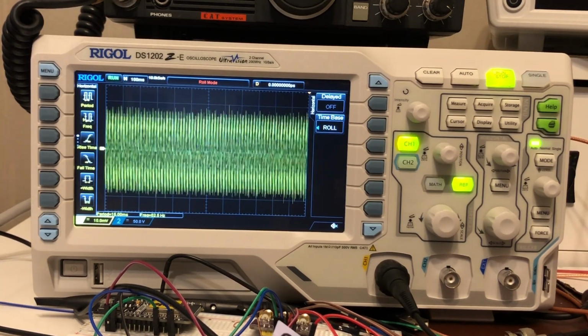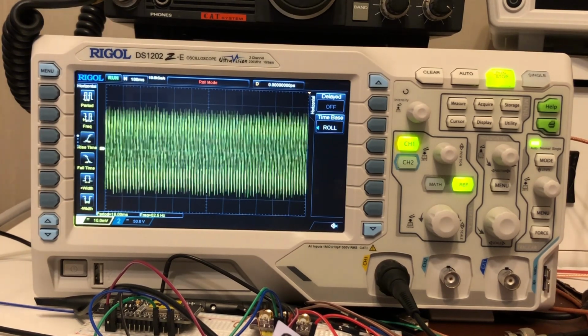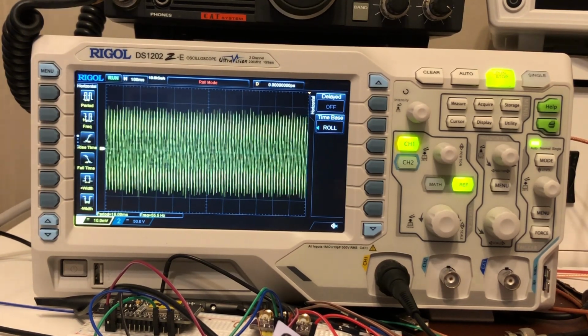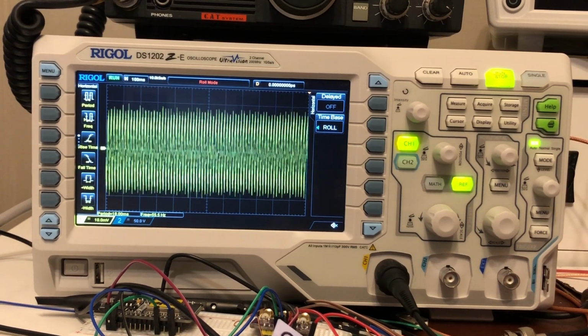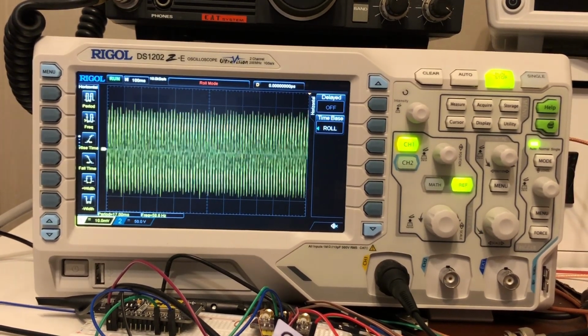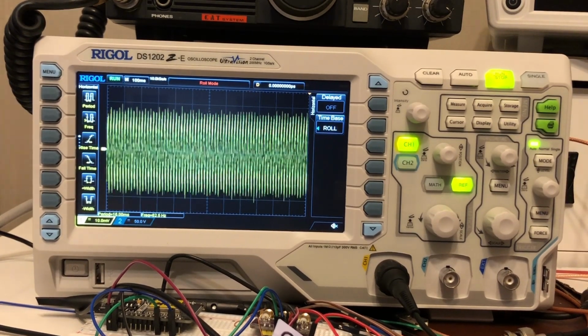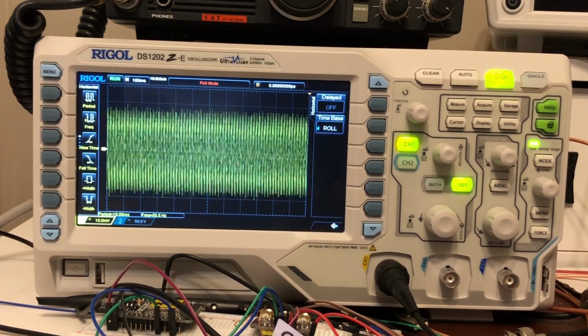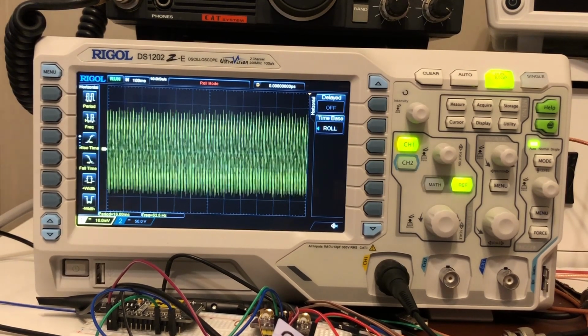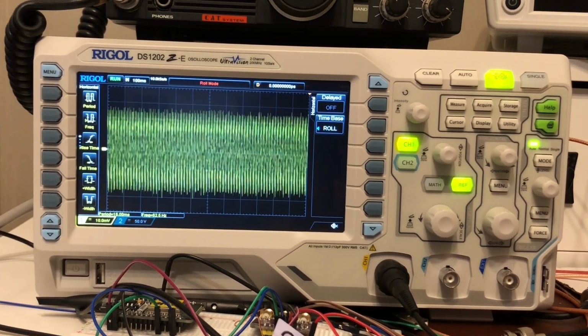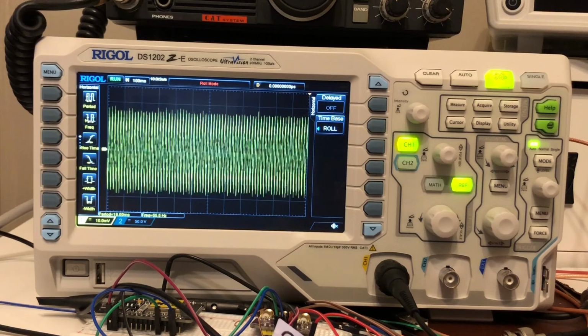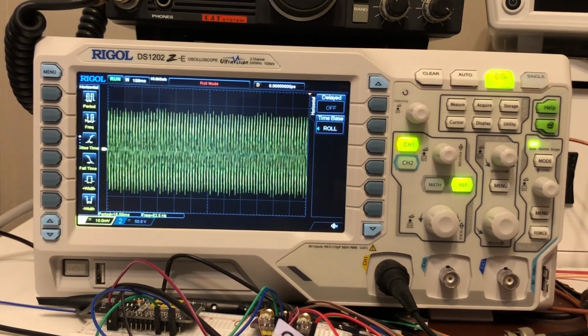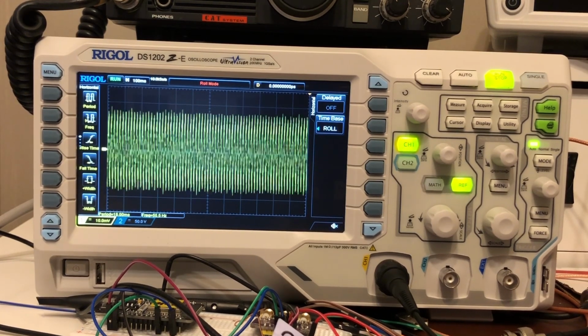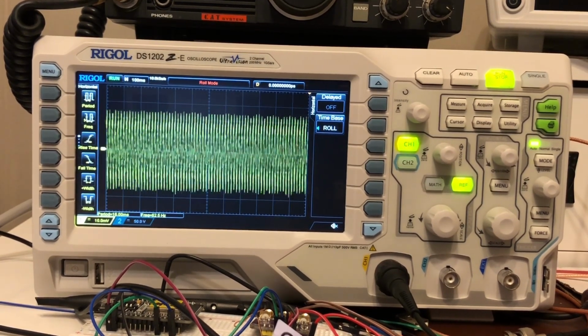Slow sweep is similar to roll mode. In YT mode, when the horizontal time base is set to 200 milliseconds per division or slower, the instrument enters slow sweep mode, in which the instrument first acquires the data at the left of the trigger point and then waits for a trigger event. After the trigger occurs, the instrument continues to finish the waveform at the right of the trigger point. When slow sweep mode is used to observe low frequency signal, DC channel coupling mode is recommended.